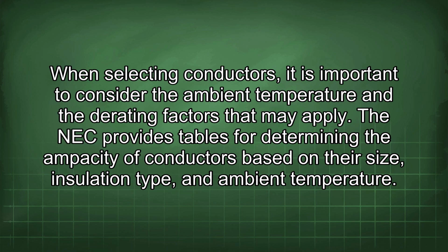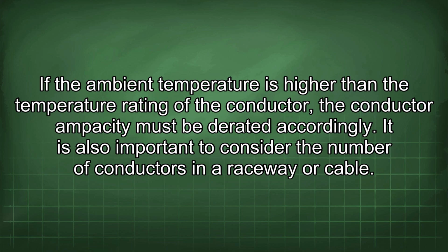When selecting conductors, it is important to consider the ambient temperature and the derating factors that may apply. The NEC provides tables for determining the ampacity of conductors based on their size, insulation type, and ambient temperature. If the ambient temperature is higher than the temperature rating of the conductor, the ampacity must be derated accordingly.